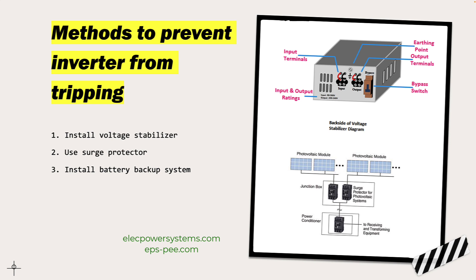It is also important to ensure that the inverter is properly sized for the electrical load that it is intended to power. If the inverter is undersized, it may trip frequently or fail to operate at all. Conversely, if the inverter is oversized, it may be more prone to tripping due to sudden fluctuations in voltage.